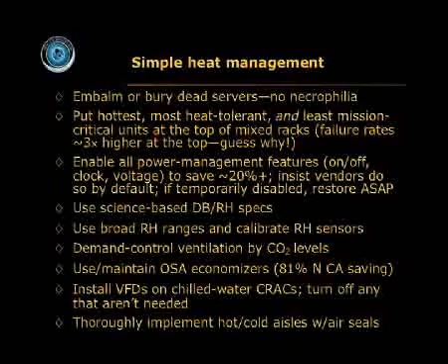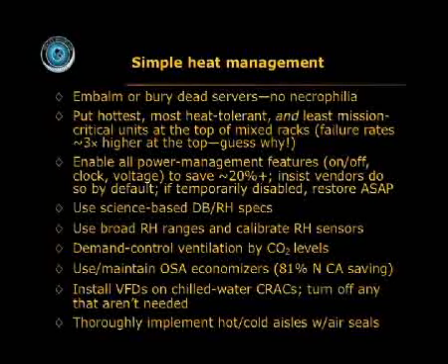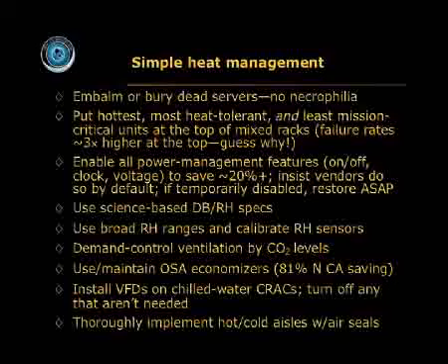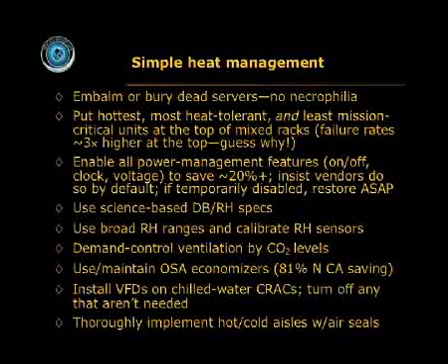Many people assume very stringent criteria for both dry bulb temperature and relative humidity in data centers. Where do the numbers come from? Well, they don't come from the equipment manufacturers. If you go back to the original specs, you find they're often much more tolerant of those wide operating conditions than the operators assume. In fact, we had a case many years ago with a Shell data center whereby mil-speccing the equipment at a modest extra cost, we were able to get enormous environmental ranges to be permitted, and we saved a lot of money up front by taking mechanicals out because we didn't need such stringent operating conditions.